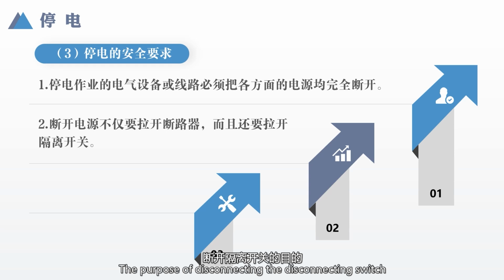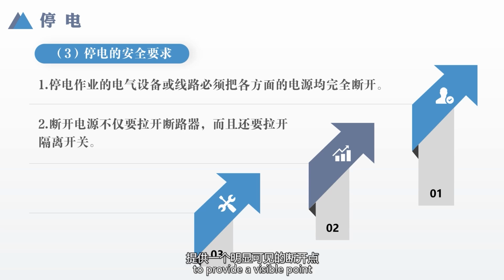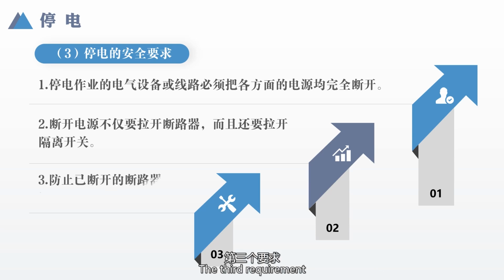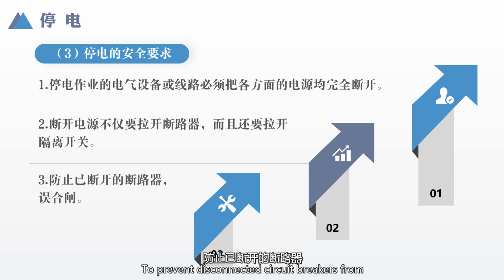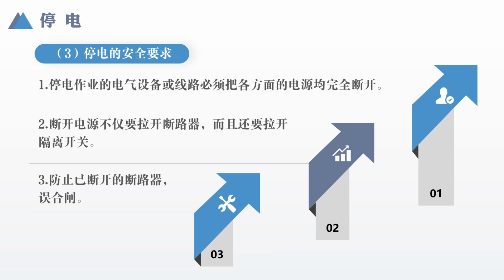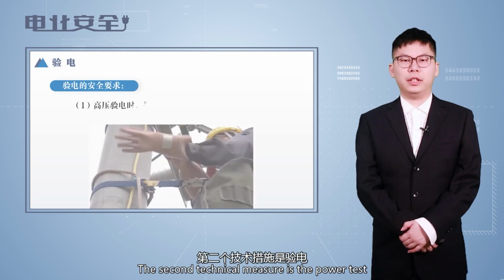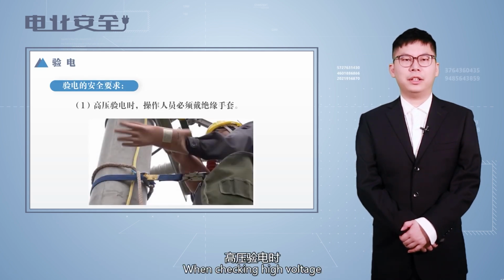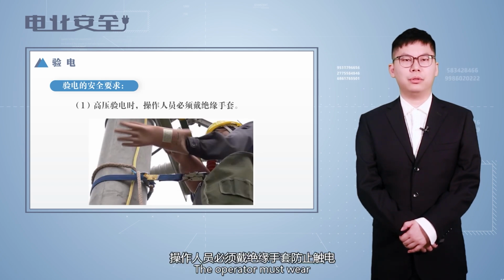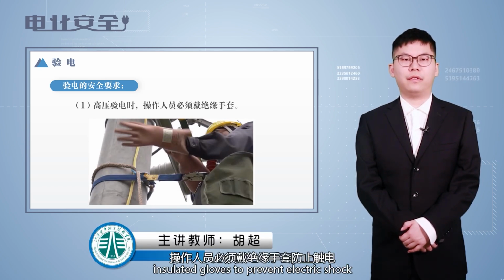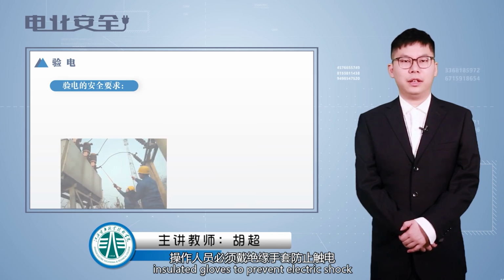The purpose of disconnecting the disconnecting switch is to separate the energized equipment between energized and de-energized equipment to provide a visible point. The third requirement, to prevent disconnected circuit breakers from being closed inadvertently. The second technical measure is the power test. When checking high voltage, the operator must wear insulated gloves to prevent electrical shock.